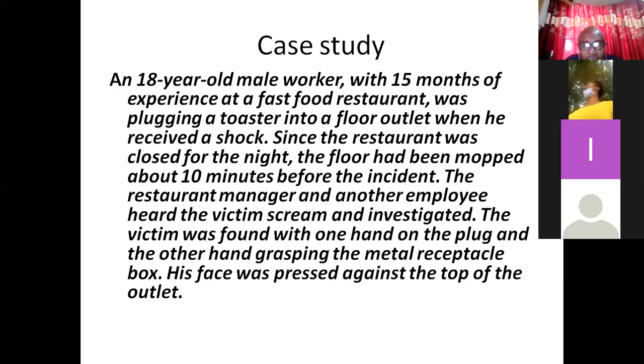Let's look at it. They said a male worker who has worked in a restaurant for 15 months was plugging a toaster into a floor outlet, and he received a shock. You can see, they said that place was mopped 10 minutes before. The cleaner just mopped it with water 10 minutes before, and he now decided to go and plug a toaster.